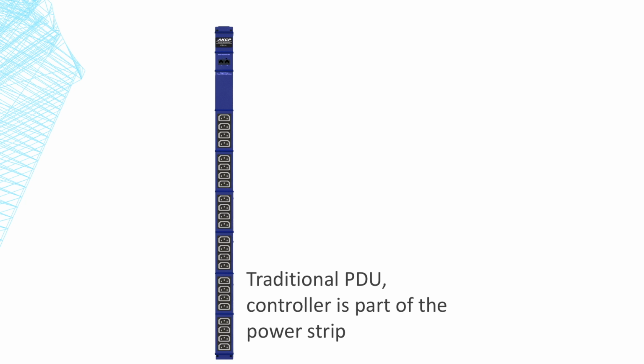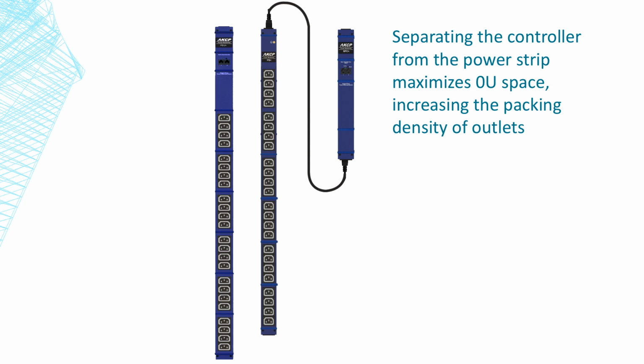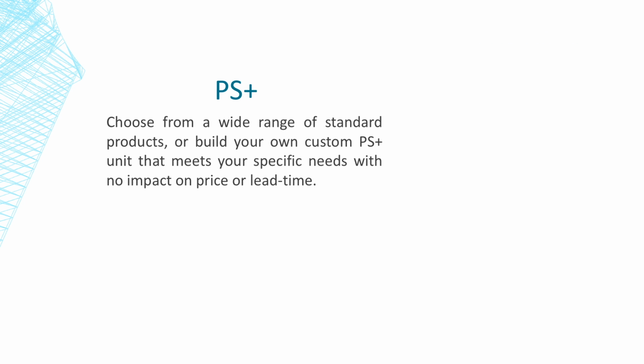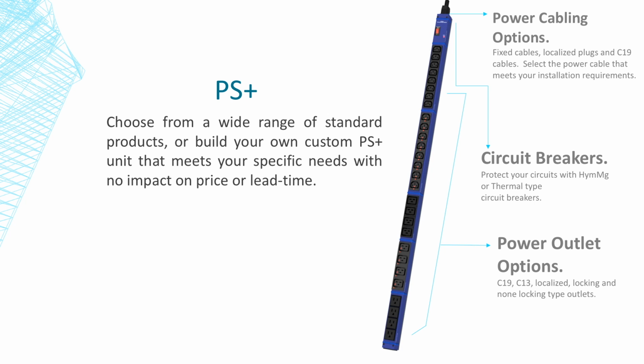The advantage of moving the power strip and power meters into separate units is that it maximizes the available zero-U space for outlets. You can see here we can fit significantly more outlets on the power strip when the controller is moved to another 0U or 1U device. For those customers who require no monitoring, we can also provide the PS Plus, a basic power strip. Choose from a wide range of standard configurations or build a custom unit with just the outlets that you need.